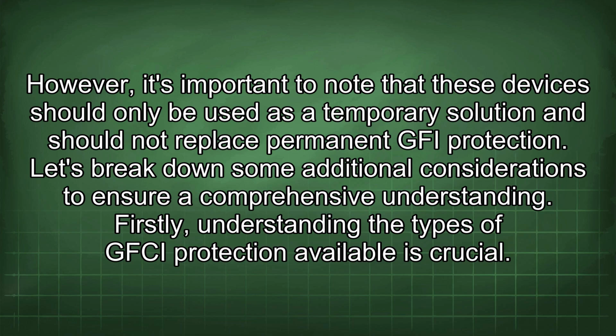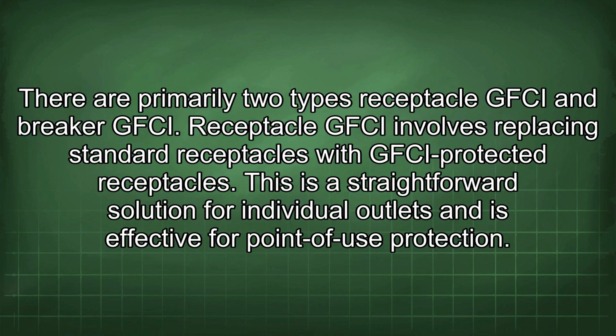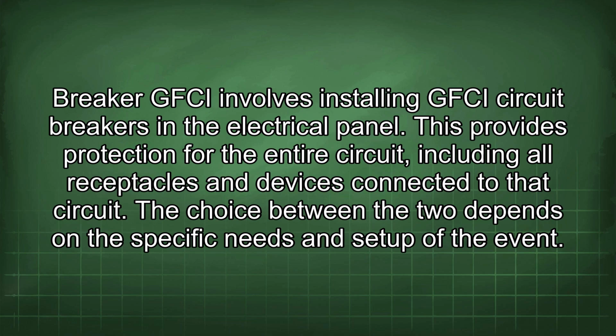Firstly, understanding the types of GFCI protection available is crucial. There are primarily two types: receptacle GFCI and breaker GFCI. Receptacle GFCI involves replacing standard receptacles with GFCI protected receptacles. This is a straightforward solution for individual outlets and is effective for point-of-use protection. Breaker GFCI involves installing GFCI circuit breakers in the electrical panel. This provides protection for the entire circuit, including all receptacles and devices connected to that circuit.